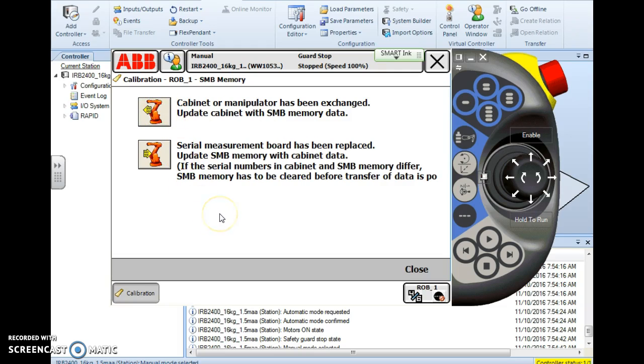The bottom option: the SMB serial measurement board has been replaced or the battery's dead or there's some type of malfunction. With the second option, we can update the SMB memory with the cabinet data. Basically, we're transferring or copying the values from the cabinet or the PC to the SMB. It's a pretty easy process.